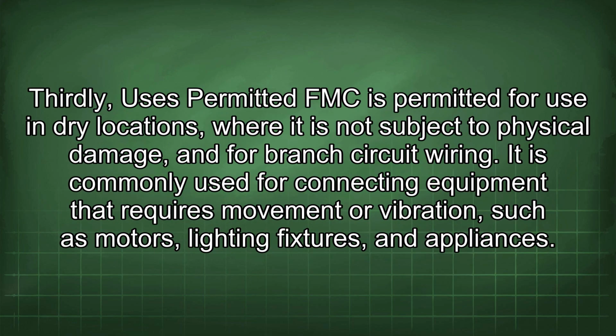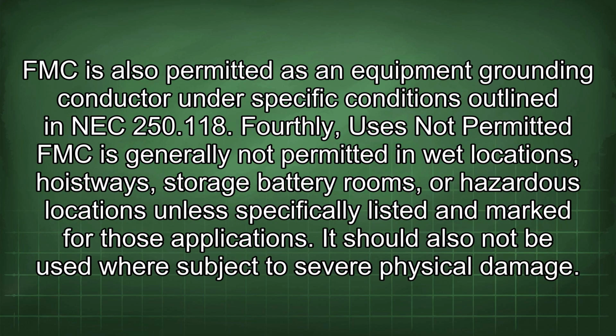Thirdly, uses permitted. FMC is permitted for use in dry locations where it is not subject to physical damage, and for branch circuit wiring. It is commonly used for connecting equipment that requires movement or vibration, such as motors, lighting fixtures, and appliances. FMC is also permitted as an equipment grounding conductor under specific conditions outlined in NEC 250.118. Fourthly, uses not permitted. FMC is generally not permitted in wet locations, hoistways, storage battery rooms, or hazardous locations unless specifically listed and marked for those applications. It should also not be used where subject to severe physical damage.